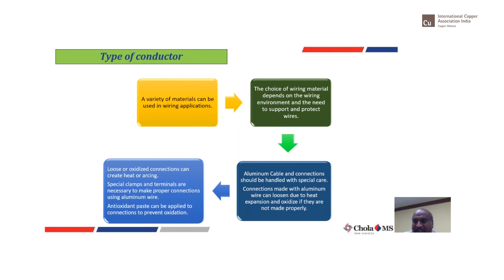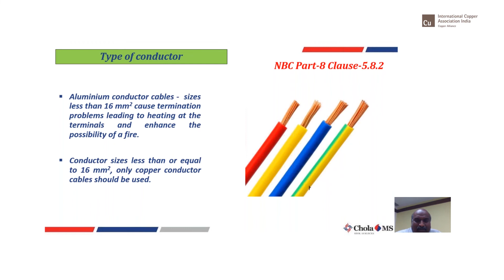As for the type of conductors, I'm not going to go more into it. Just be assured that for anything lesser than 16 square mm, please do not go for aluminum. Always use copper when the sizes are going down, meaning the lower the size, the better it is to use copper. One reason is flexibility. Second, if you bend aluminum twice or thrice, it might break. Copper is more flexible, still carries a little bit more current, and is safer.